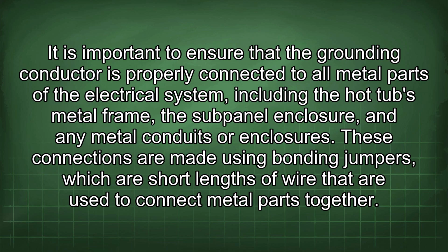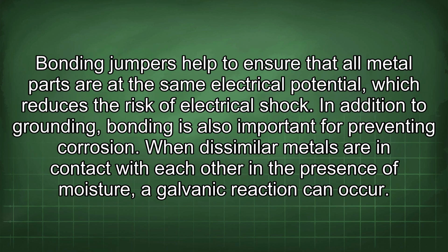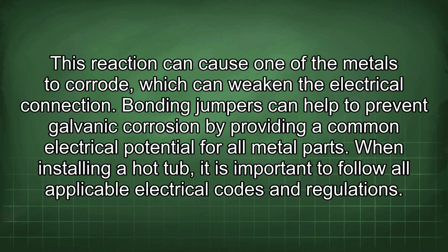These connections are made using bonding jumpers, which are short lengths of wire that are used to connect metal parts together. Bonding jumpers help to ensure that all metal parts are at the same electrical potential, which reduces the risk of electrical shock. In addition to grounding, bonding is also important for preventing corrosion. When dissimilar metals are in contact with each other in the presence of moisture, a galvanic reaction can occur. This reaction can cause one of the metals to corrode, which can weaken the electrical connection. Bonding jumpers can help to prevent galvanic corrosion by providing a common electrical potential for all metal parts.